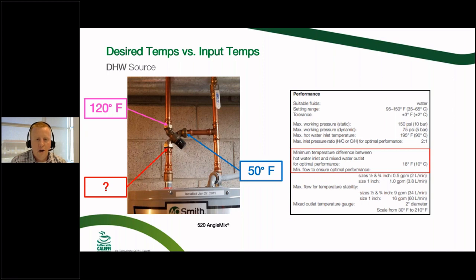And you'll notice here with our 520 series angle mix, we have a minimum temperature difference of 18 degrees. Now that's not to say that it's not going to work with a temperature difference that's a little bit lower, say 15 degrees or 14 degrees. I have found that some of these numbers are a little bit on the conservative side, but in order to get the most effective and optimum performance out of that mixing valve, that 18 degrees is something that you're going to want. And where the phone calls usually come into play is when they've installed this new domestic hot water system, a storage tank or a water heater, they put this mixing valve in, and they're not getting 120 out of it.